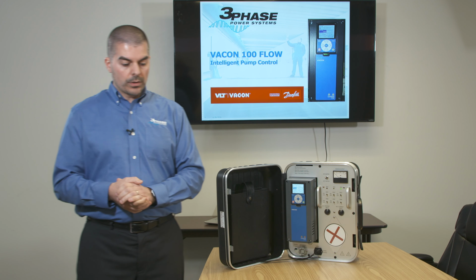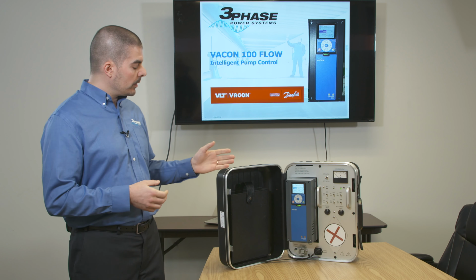The other thing that I wanted to discuss is that the software inside this drive is very unique. What separates this software from these drives to others is the fact that we have a pump controller inside the drive, and we don't need a pumping relay. We don't need these external components that are traditionally used for other regular drives.